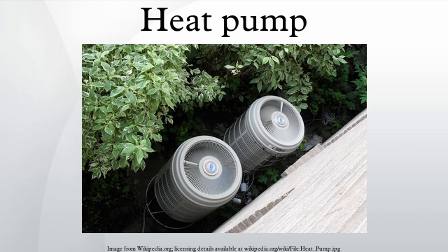Applications. HVAC. In HVAC applications, a heat pump is typically a vapor compression refrigeration device that includes a reversing valve and optimized heat exchangers so that the direction of heat flow may be reversed. The reversing valve switches the direction of refrigerant through the cycle and therefore the heat pump may deliver either heating or cooling to a building. In cooler climates, the default setting of the reversing valve is heating. The default setting in warmer climates is cooling.